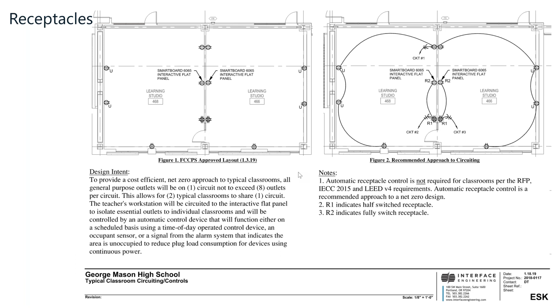So in the room, that works very similar to the lighting, where the teacher would come in and turn those computers on and turn the smart board on to use it. And then once the room is vacated, the occupancy sensor, that same controller that's controlling the lights, will actually turn off the smart boards. We thought that was important because there's so many electronics happening within those 60+ learning studios. That was important not to just turn them off when they were not in use, but to turn off the phantom loads as well. So they're not running 24/7, 365, even in the phantom loads. So we were able to reduce our receptacle loads within the classroom by having those shut down.